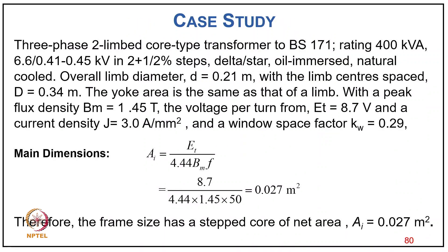Design case study: a 3-phase, two-limb, core-type transformer, BS171 rating 400 kVA, 6.6 kV / 0.414 kV (in ±2×1/2 steps), delta-star, oil-immersed natural cooling. Overall limb diameter d = 0.21 m, limb center spacing D = 0.34 m, yoke area same as limb area. Peak flux density Bm = 1.45 T, volt per turn ET = 8.7 V, current density J = 3.0 A/mm², window space factor Kw = 0.29.